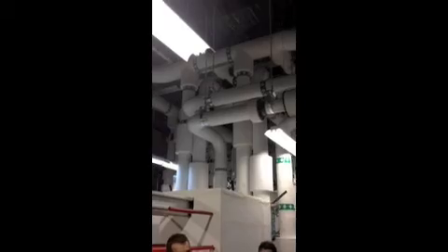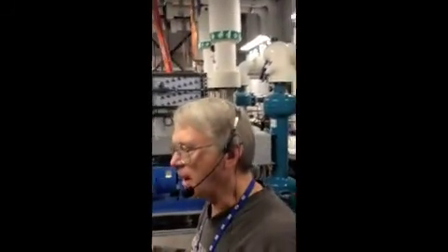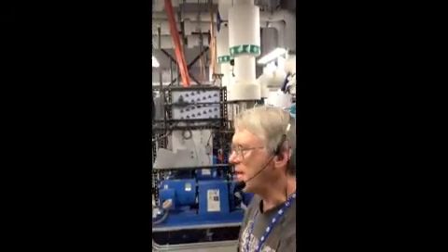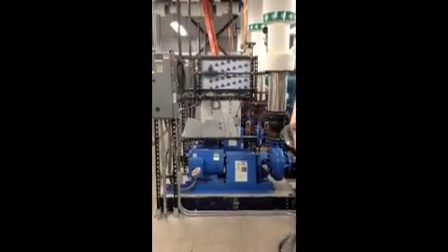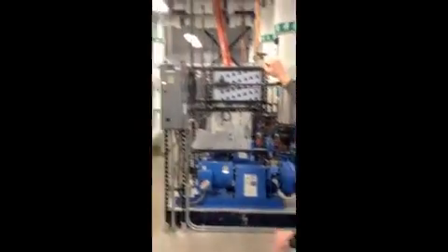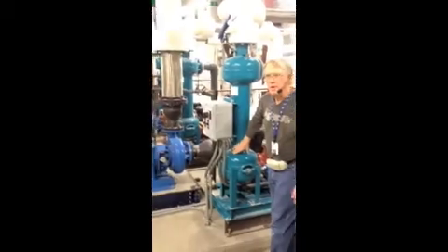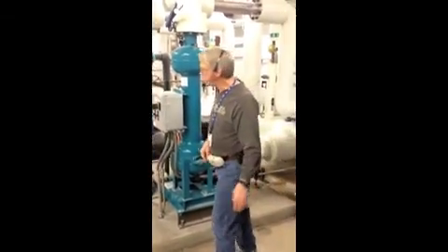The reason you have primary and secondary is that the primary loop out here is open to the air. When you're using cooling towers, you actually are blowing a lot of air through there to evaporate the water. You have dirt, leaves, everything else, and it accumulates in there. So that water has to be cleaned regularly. The dolphin systems are supposed to keep things in suspension. And here you have a centrifugal pump that spins out particles and then gets purged out regularly.